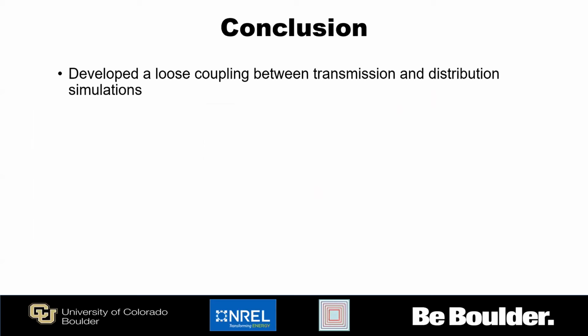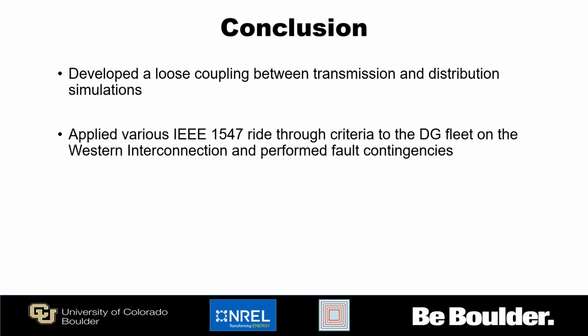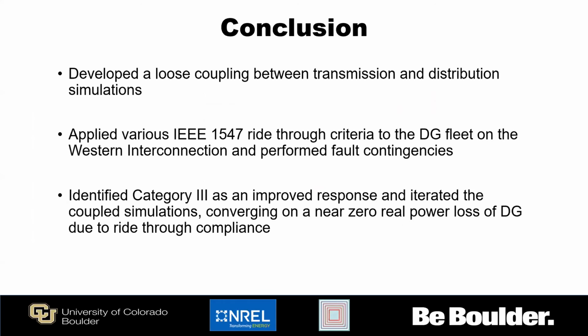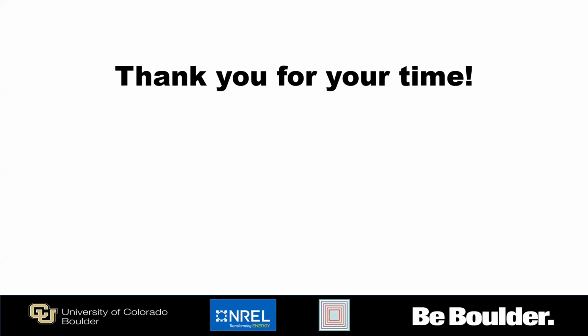So what we've done here is we've developed a loose coupling simulation between the transmission and distribution system simulations and use this to look at the impact of the various IEEE 1547 ride-through criteria and their impact on the distributed generation fleet in the Western Interconnection. And so compliance with category 3 provides a much improved response as opposed to category 1, category 2, or the 1547-2003 case, converging to, in this case, a near zero real power loss of DG for this very large fault in the Western Interconnection. So thank you very much, everyone, for the time.